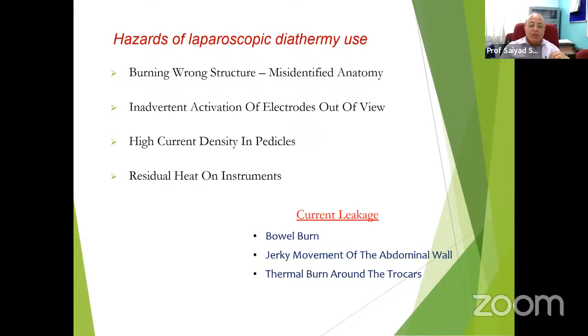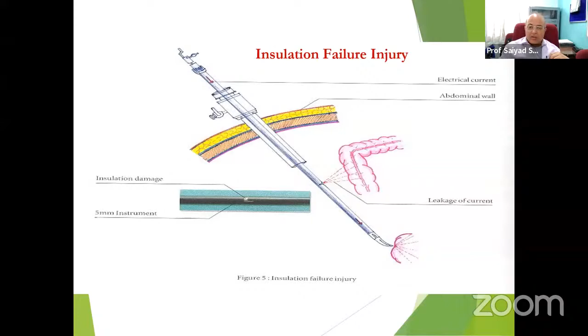You see here insulation failure. As I told you earlier, there is a cautery hook. If there is any wear and tear, for example insulation damage, then when you introduce the 5 mm instrument and go to the target organ for dissection or coagulation, current also leaks from the insulation damage. You damage the bowel or any other part of the abdomen. That should be considered a hazard.